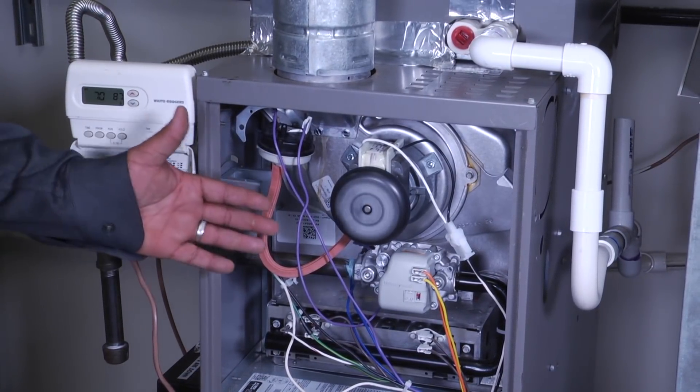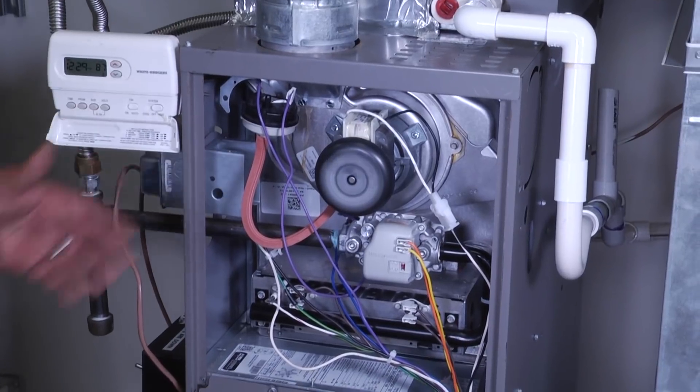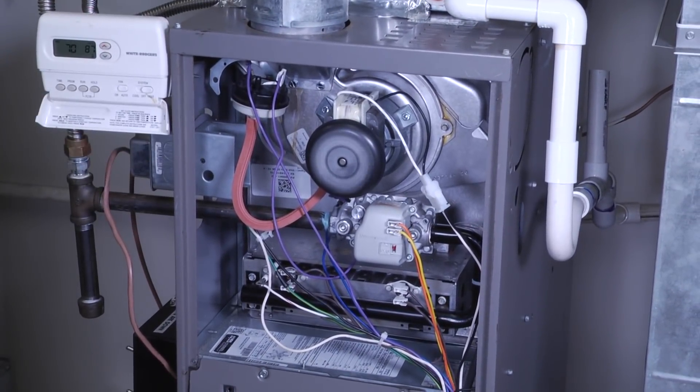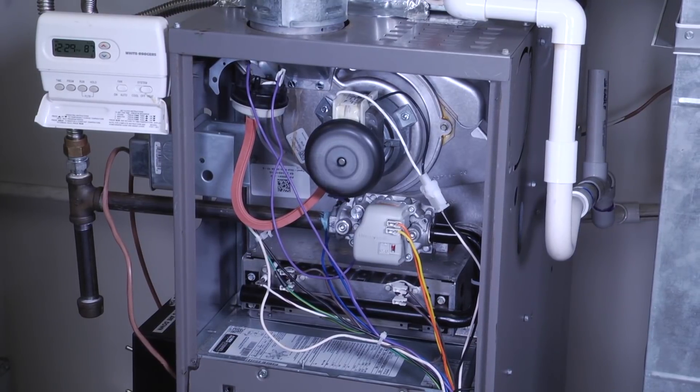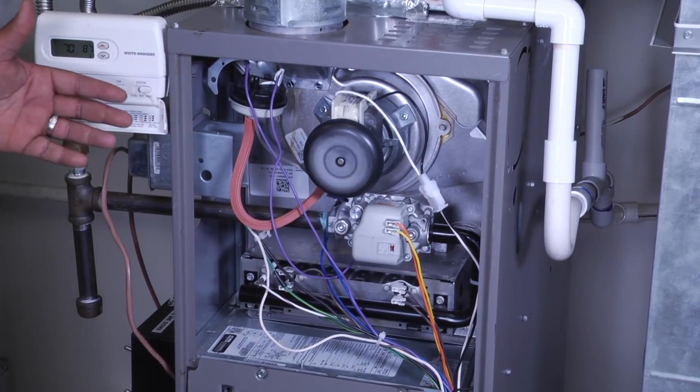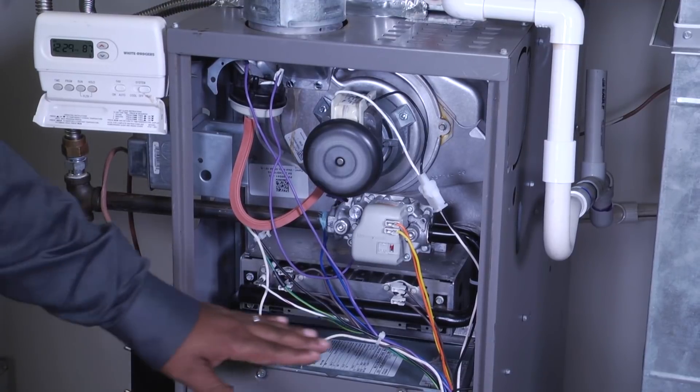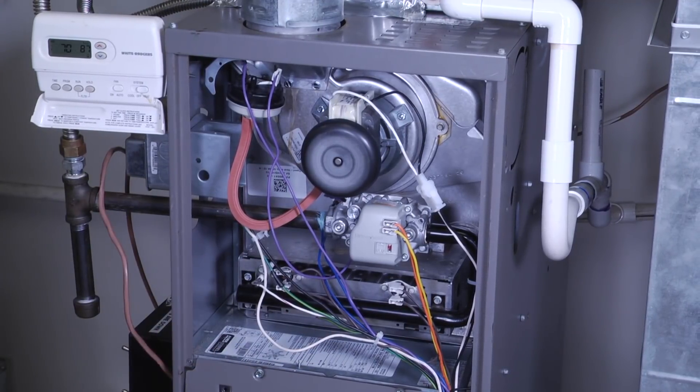So there's our inducer motor. Our inducer motor starts. Once our inducer motor starts, our pressure switch is going to say okay, my inducer motor is running, I'm good to go, there's no cracks or leaks anywhere. And then shortly after that, we're going to get a glow inside our burner housing down here from our hot surface igniter.